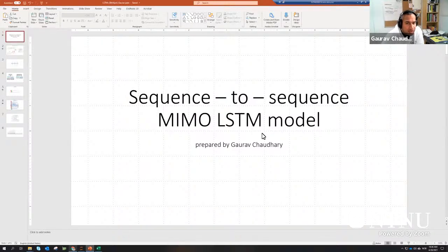So in the building industry, I need to predict for controls. I need to predict the indoor temperature or some other parameter about a room, about a building, for the next at least 1 day. That goes into the model predictive control, the horizon control, and it determines the best options for controls for heaters, for supply temperature of air handling units, for chiller and/or boiler working. So we need to predict some future time steps, and research says that it has to be at least 1 day.